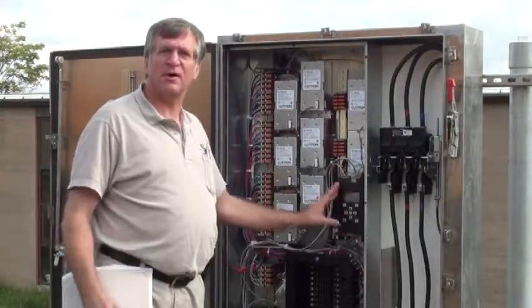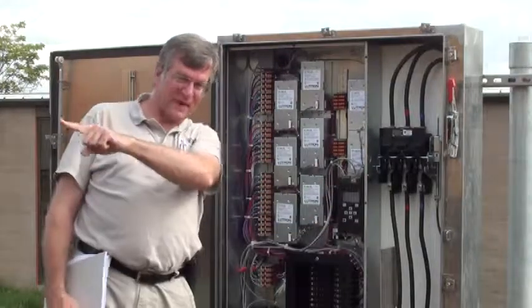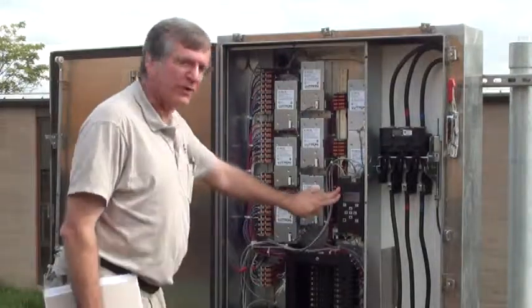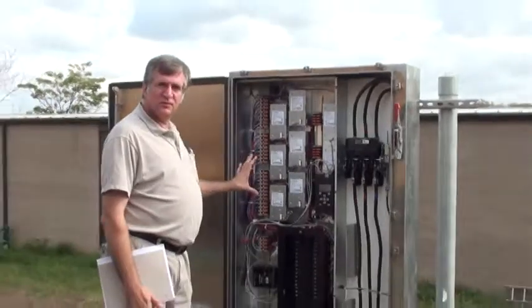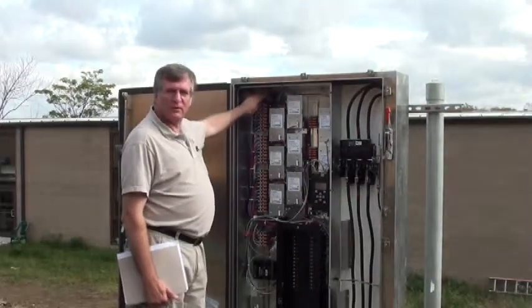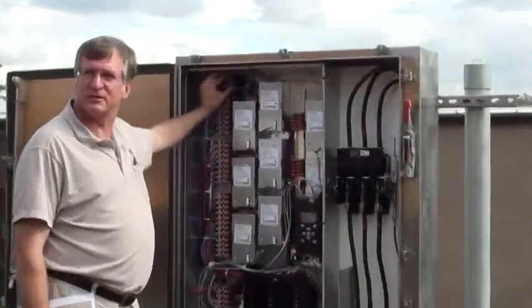You'll never actually use this unit. You'll do all your programming from panel 1, which is that direction if you're keeping up with where we're at in the field. The main reason we're showing you this is up in the corner here is your actual temperature sensor that's going to determine at what point you turn on and off.